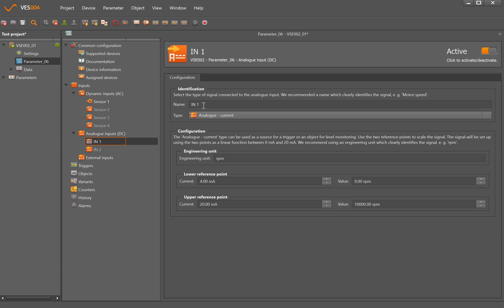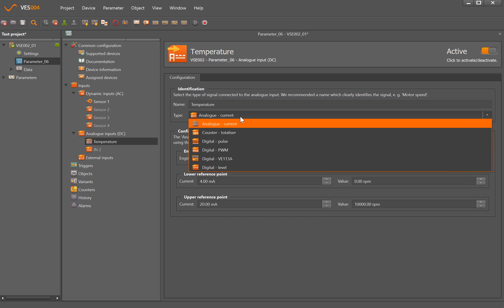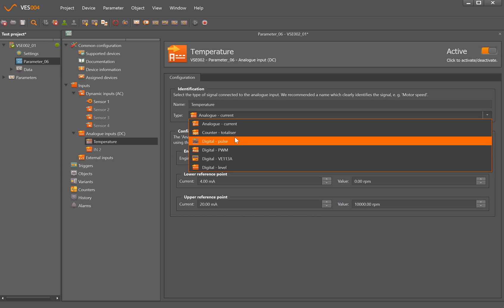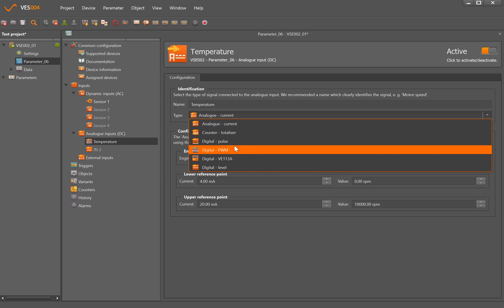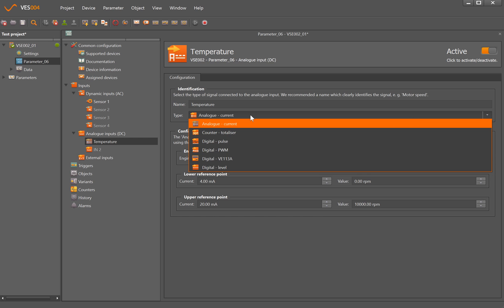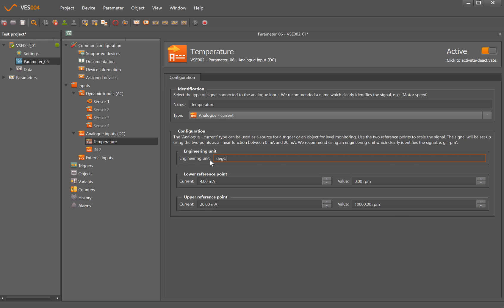So input 1 I'm going to change that to temperature so it means a bit more when I look in my parameter set here. It's an analog current but we also have ability to bring in like digital inputs or pulse width modulation as well, and we'll change the engineering unit to degrees C. It then asks me for the range of the sensor, so my 4 milliamp point is 0 degrees C and my 20 milliamp point in this instance will be 100.